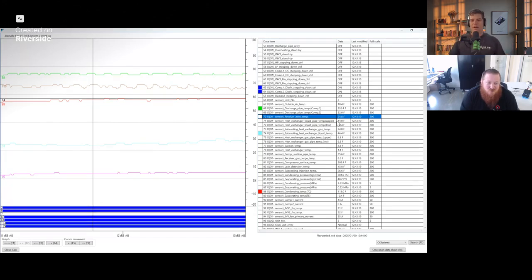Cool. What does the subcool valve do, Donald? Let's talk about that really quickly. I think it's best to then define what subcooling is in a VRF system versus a regular conventional system. Okay, go for it. The subcooling circuit in the VRF is to provide, to put a dumb word, cooled hot refrigerant. Does that make sense? Cooled, like we're bringing the temperature of that hot refrigerant down, right?